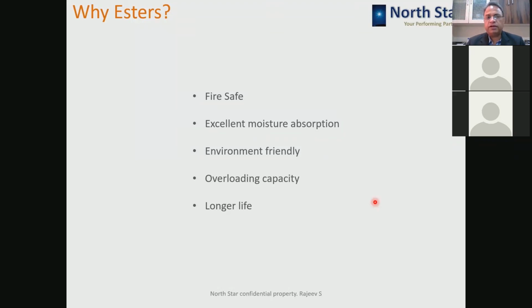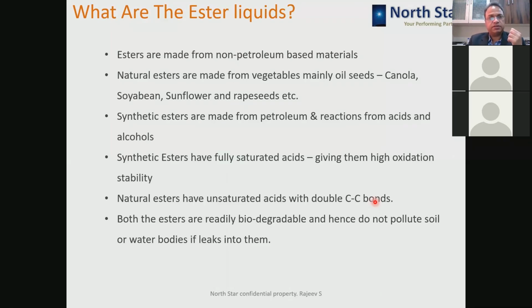And then they provide a very long life for the transformer. Many times it is found that a 2.5 to 3 times life extension happens when you opt for esters. So these are excellent properties which are not available in mineral oil, and because of these properties, the life, usability and safety of the transformer improve multifold. That's why these esters are quite preferable as far as transformers are concerned.